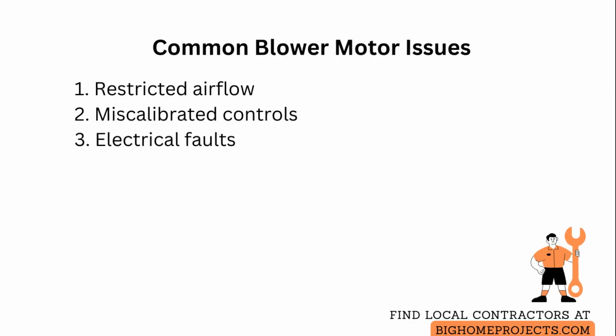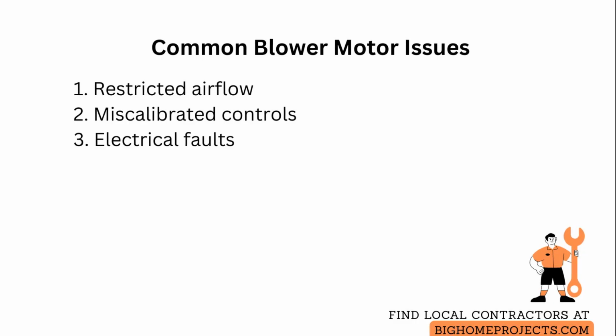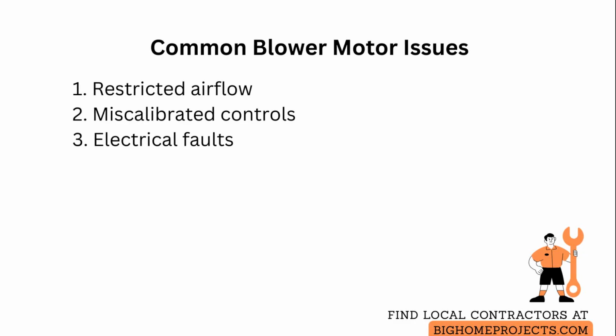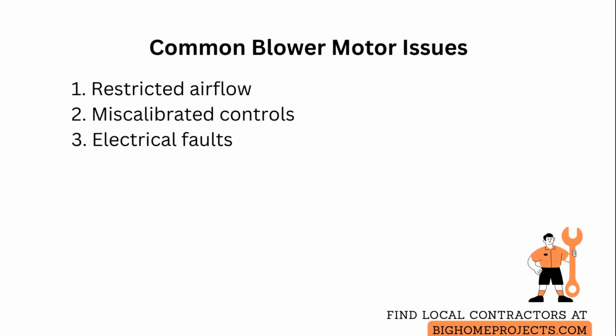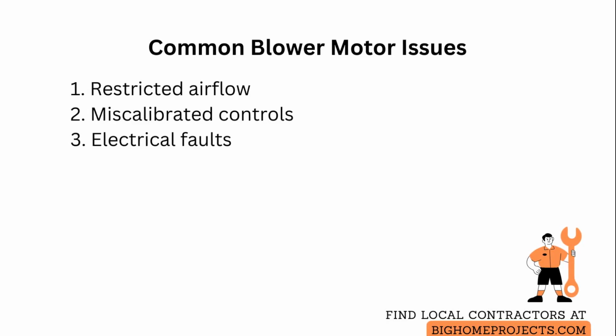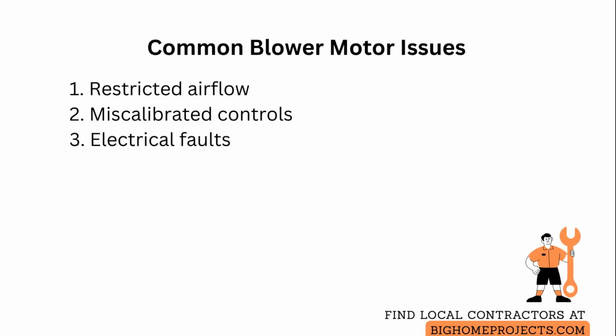If the blower runs too long because of restricted airflow, replace or upgrade filters to a lower pressure drop model and clear vents and returns to restore airflow. When the fan limit or thermostat settings are incorrect and lead to overrun, recalibrate the fan control or replace the thermostat using the manufacturer wiring diagram and test by observing cycle behavior after changes.